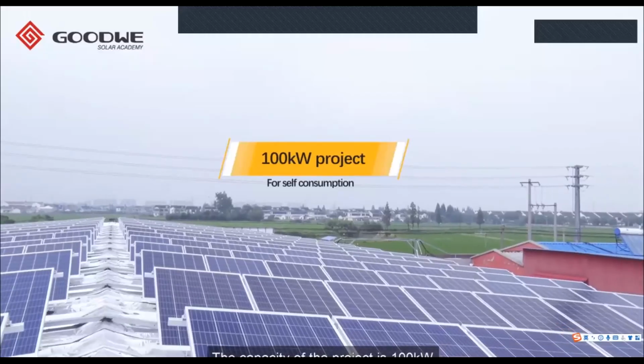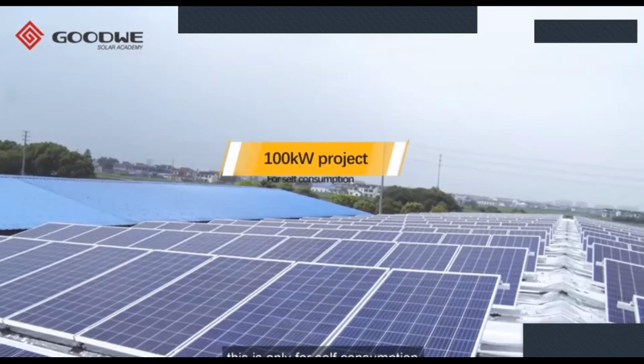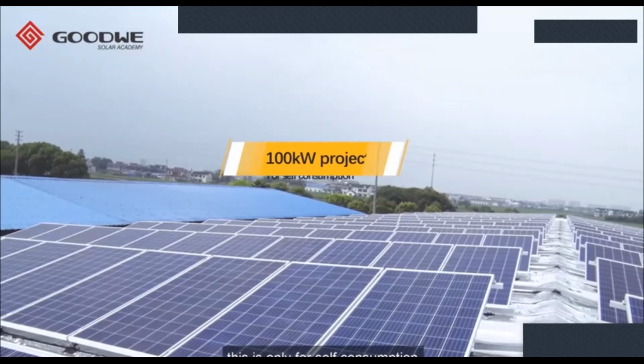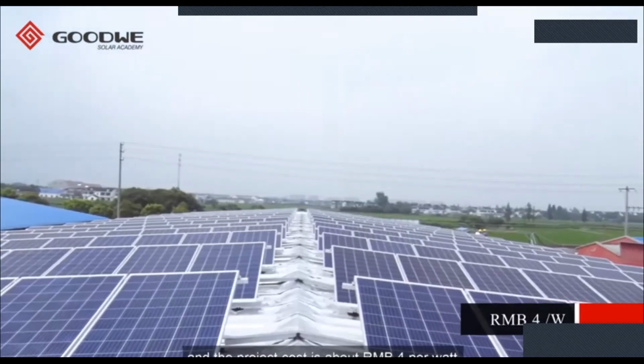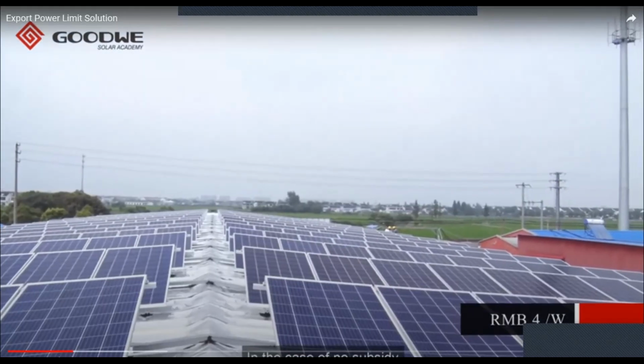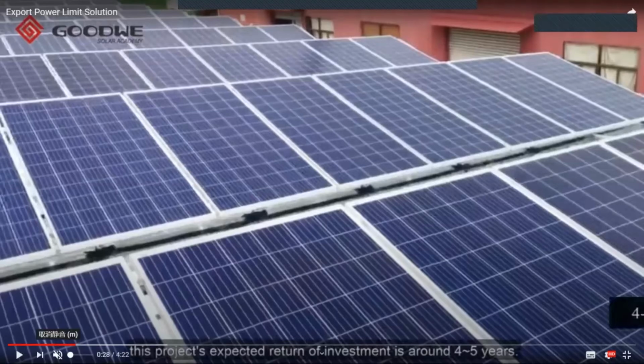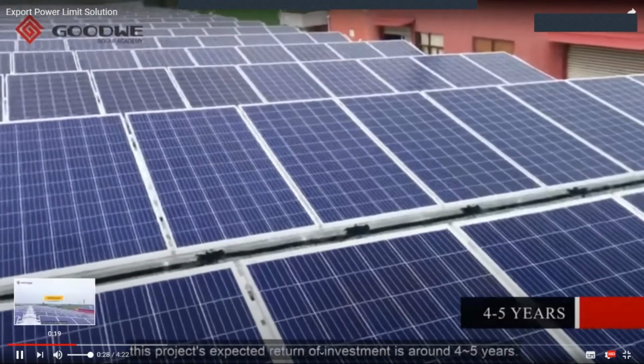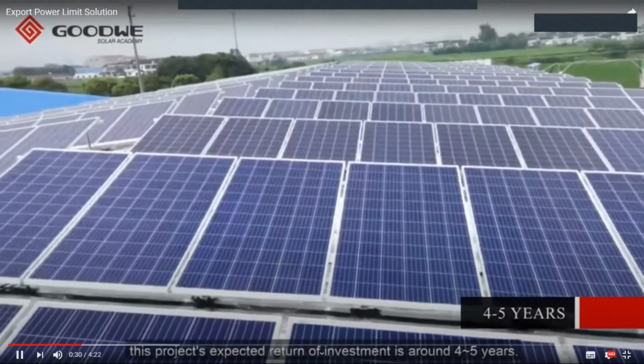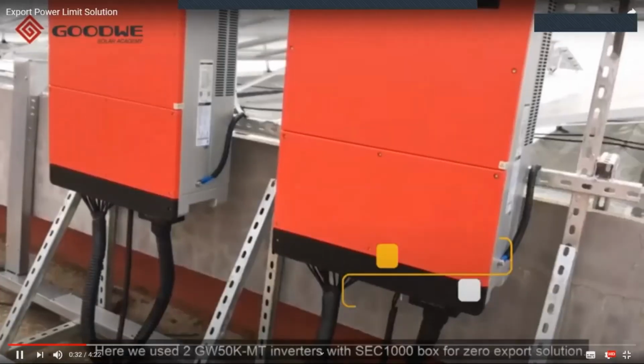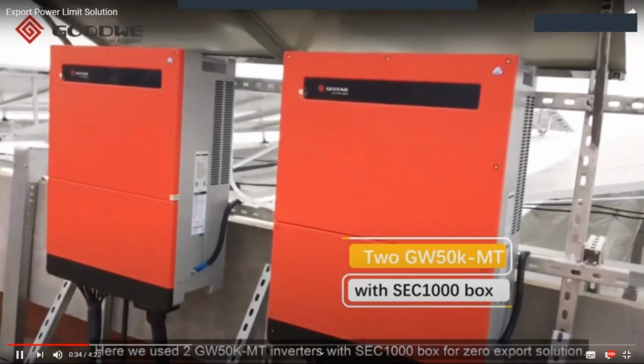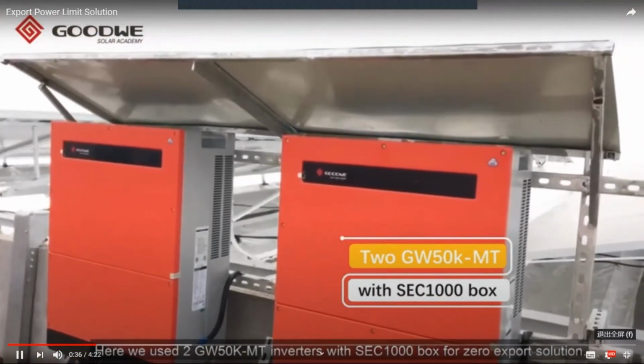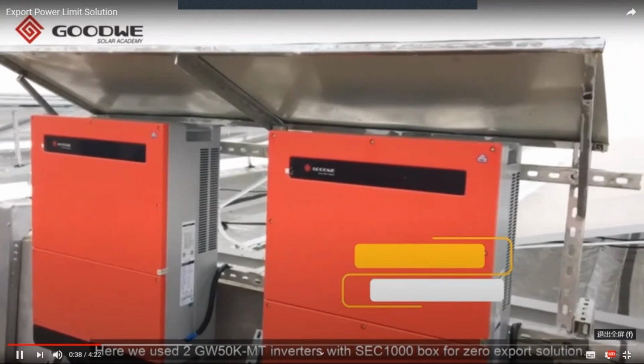The capacity is 100 kilowatt. This is only for self-consumption, not feeding the grid. The project cost is about 4 yuan per watt. In the case of no subsidy, this project's expected return on investment is around 4 to 5 years. Here we use two GW50K-MT inverters with SEC 1000 boxes for the zero export solution.